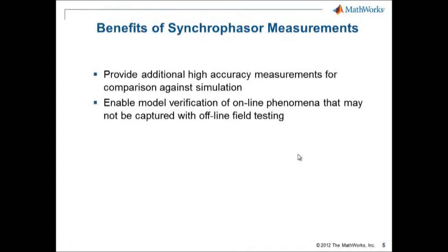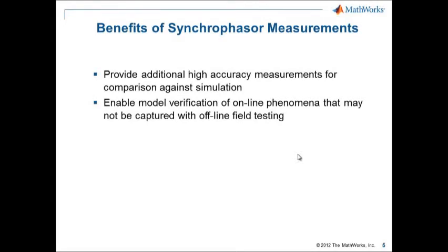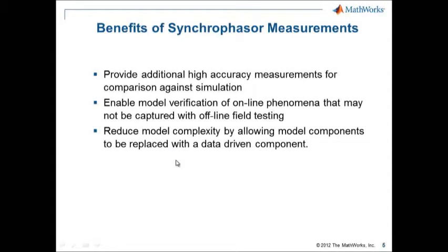To give you a classical example, a subsynchronous resonance is a phenomenon that happens when there is an interaction of the electrical resonance with the mechanical resonance. Now, that simply cannot be captured during an offline testing. So the parameters of the turbine, such as the damping or the stiffness of its shaft, those parameters cannot be validated by these offline tests. So capturing such a disturbance using phasor measurement units is highly valuable in the model verification process. And the last thing is, synchrophasors can actually allow you to reduce model complexity by replacing components like parts of the grid with data-driven component. We'll get back to this with more detailed example to show you how actually you can reduce the model complexity.